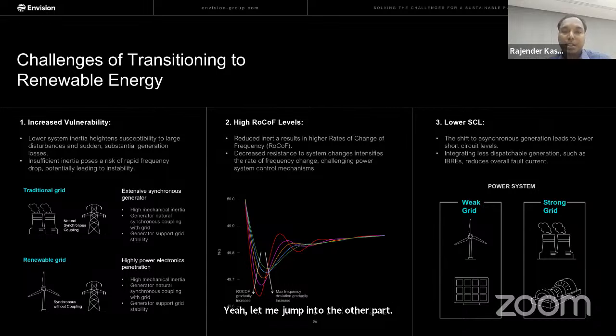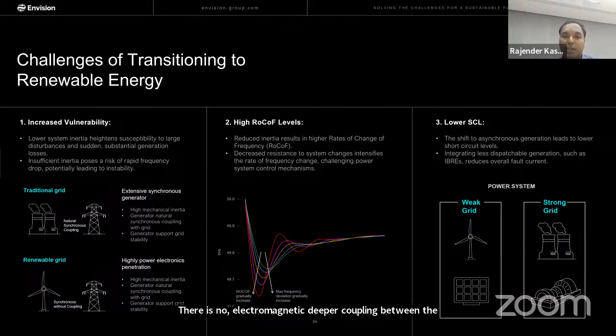As we transition from traditional energy sources to renewable energy sources, it actually decreases the system inertia. Basically, with a wind turbine or a solar PV inverter, there is no electromagnetic coupling between the grid and the generating element, which causes this reduction in inertia. What will be impacted is that you are going to lose the largest generating unit in the power system. This insufficient inertia causes a risk of rapid frequency drop, potentially causing instability in the system.